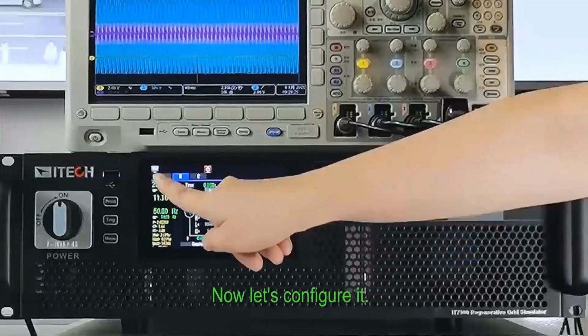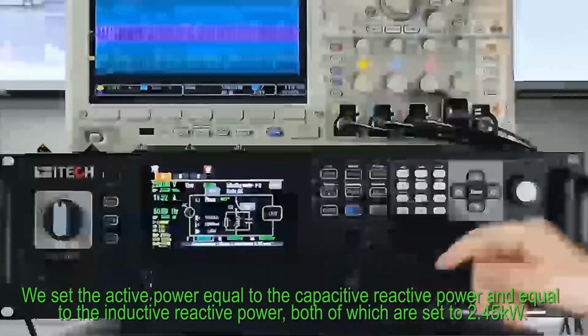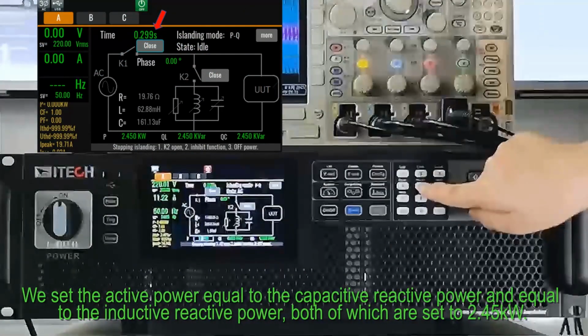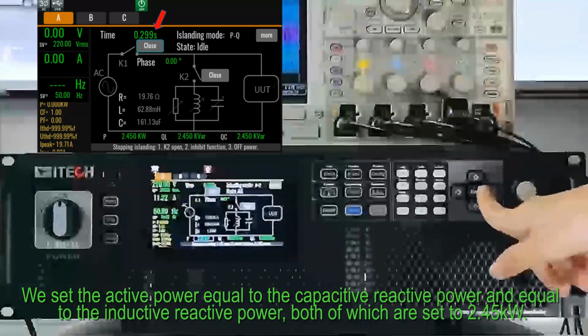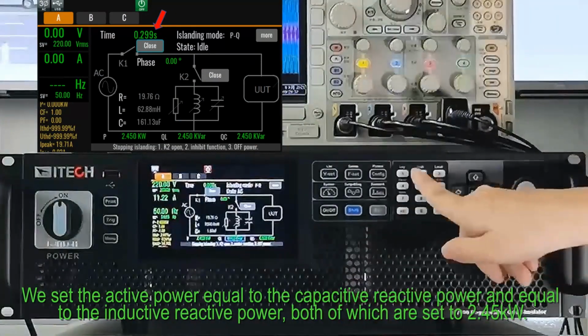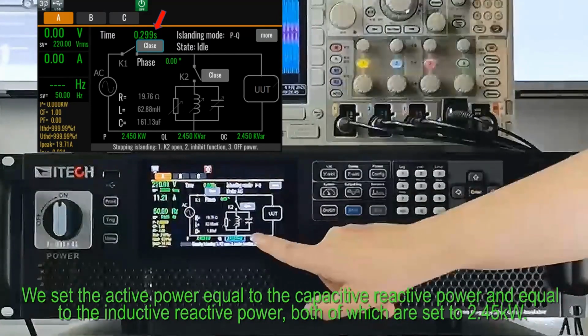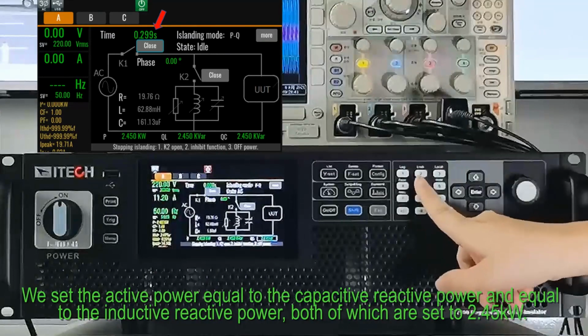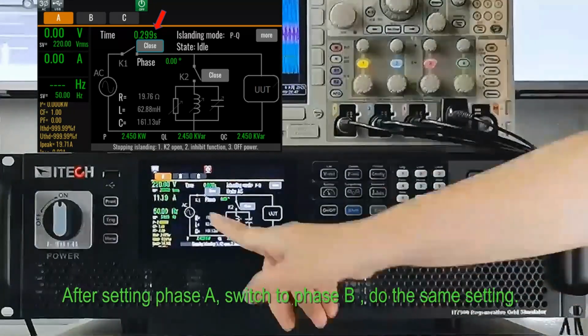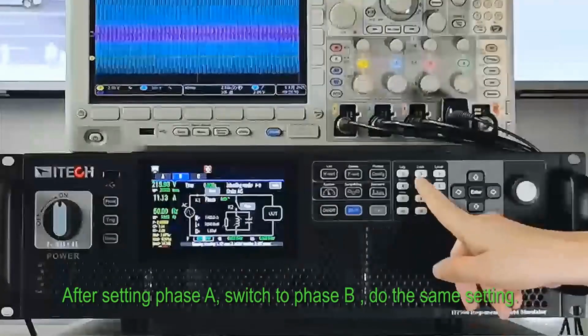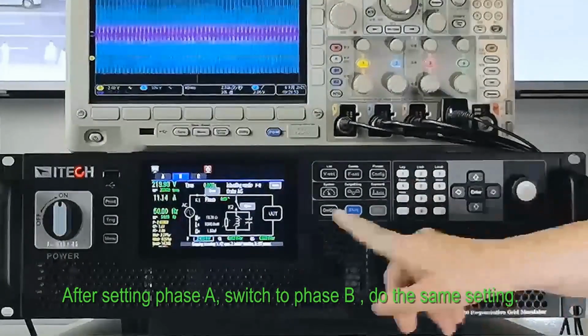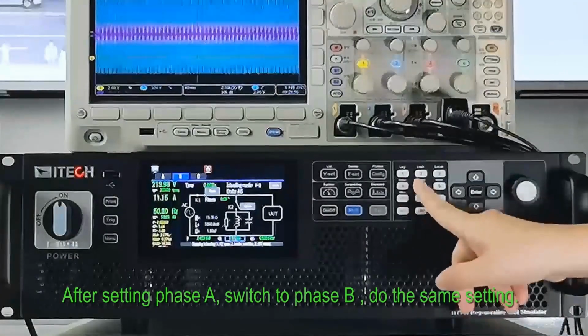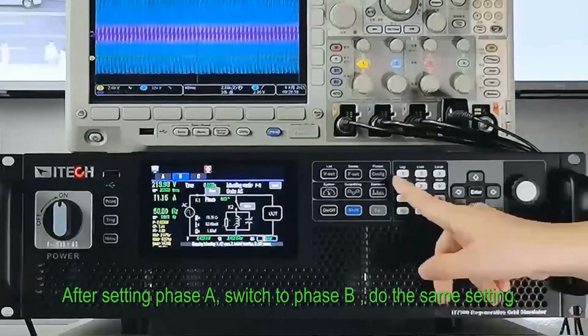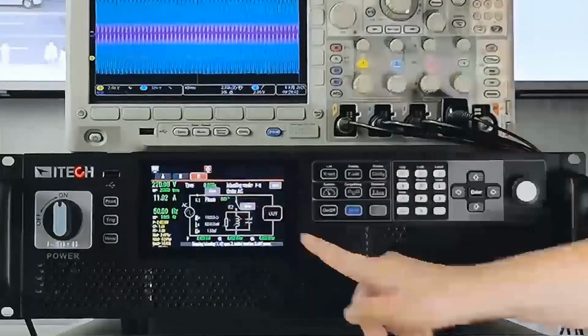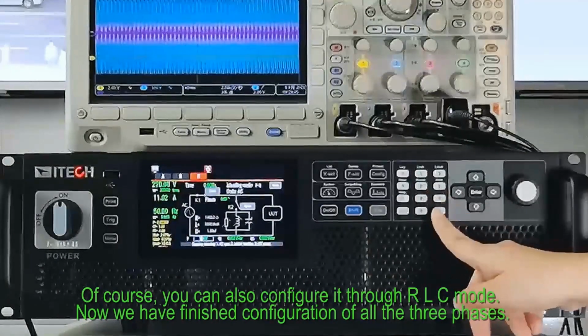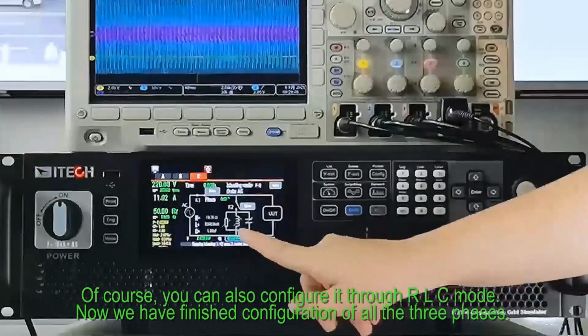Now let's configure it. We set the active power equal to the capacitive reactive power and equal to the inductive reactive power, all of which are set to 2.45 kilowatts. After setting phase A, switch to phase B, do the same setting. Of course, you can also configure it through RLC mode. Now we have finished configuration of all the 3 phases.